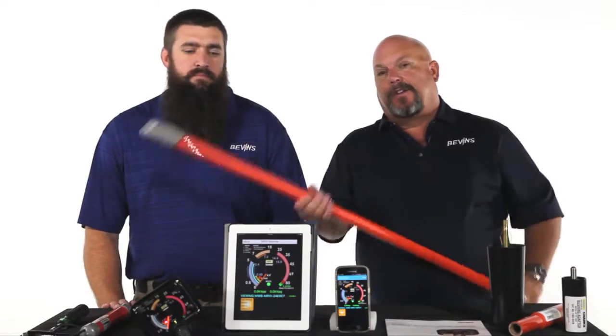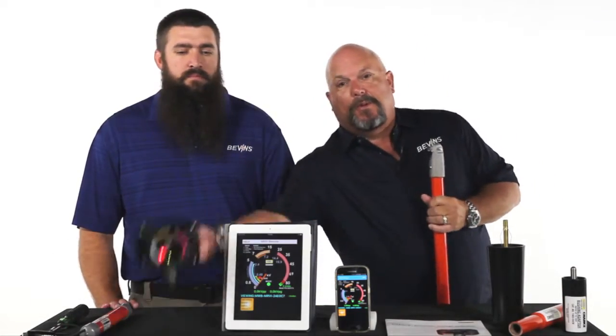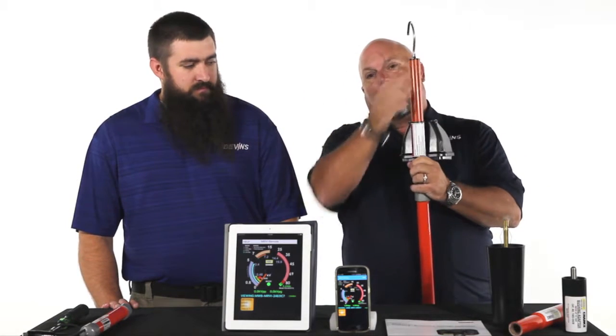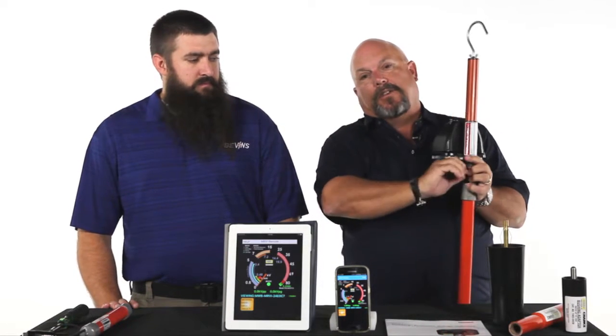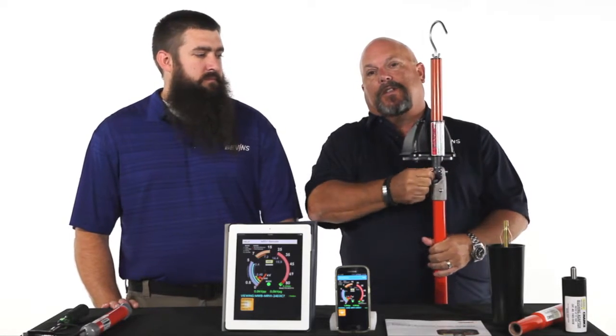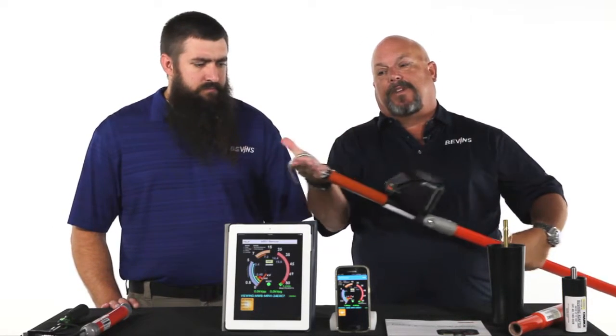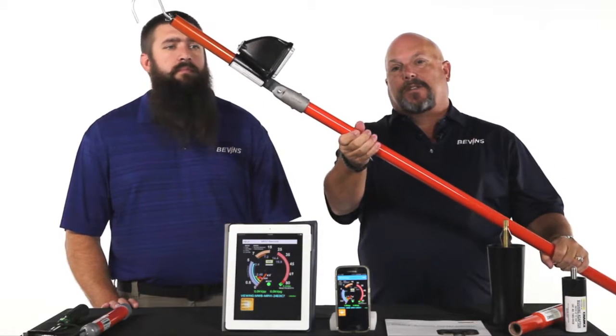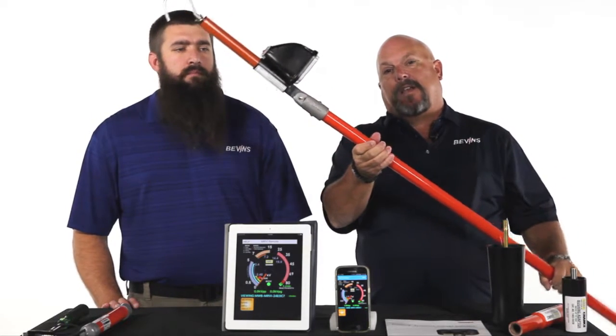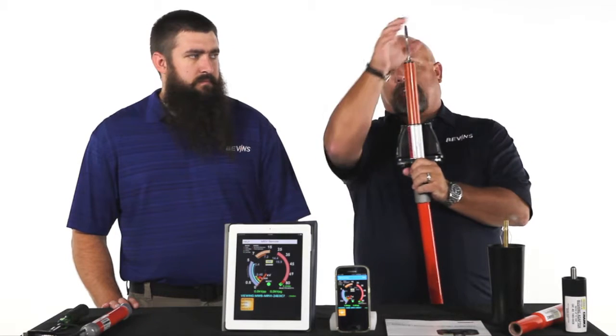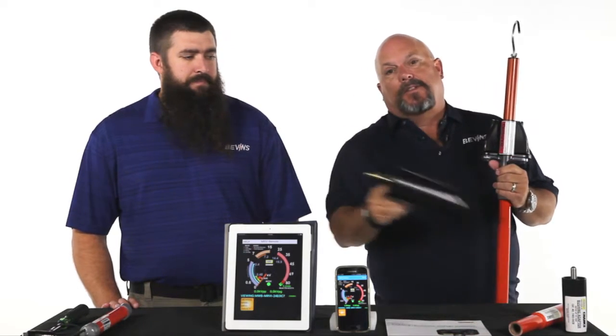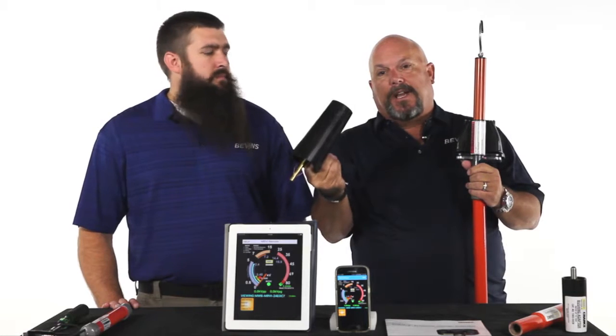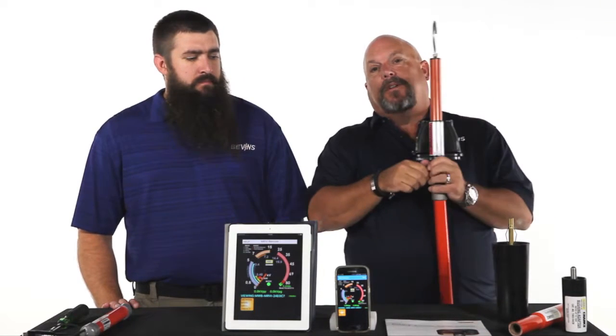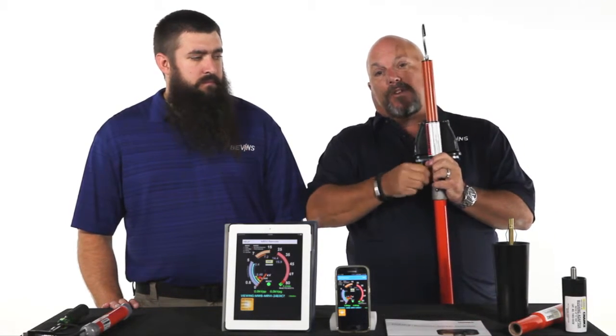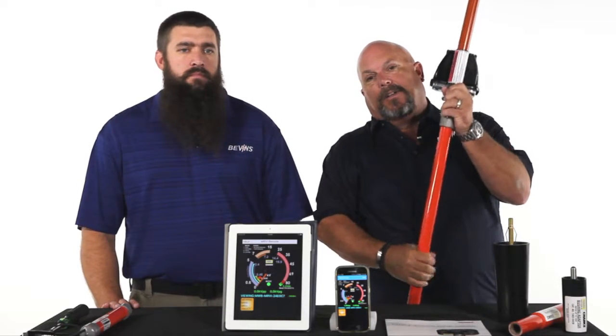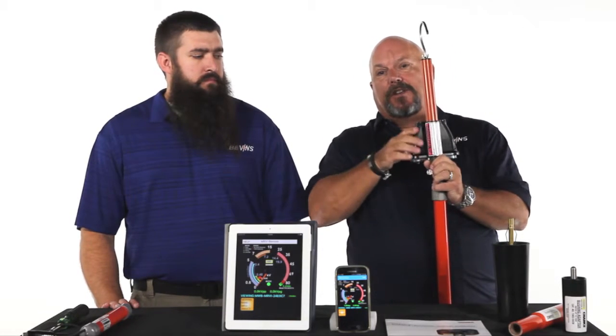As with all our indicators, you must use a universal pole, grip ball, or shotgun of appropriate length. Screw on the universal head and make sure it's good and snug. This is a contact device, so you want to use it in the middle of the span; the closer you are to a ground, the higher the readings may be. If you're using it in an underground cabinet, it's very important that you use your bushing adapter or elbow adapter of appropriate type for your safety. Always have your universal stick or shotgun attached to your indicator.